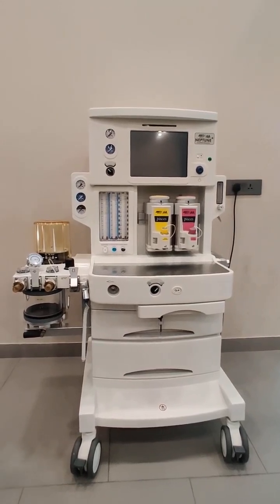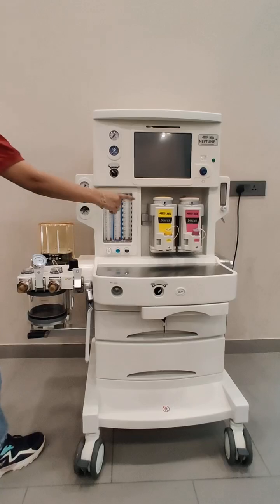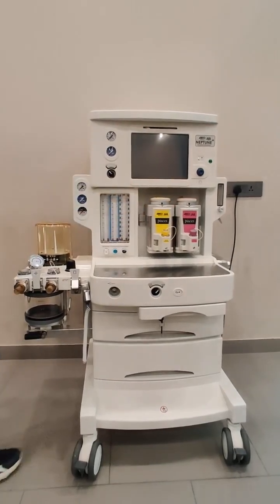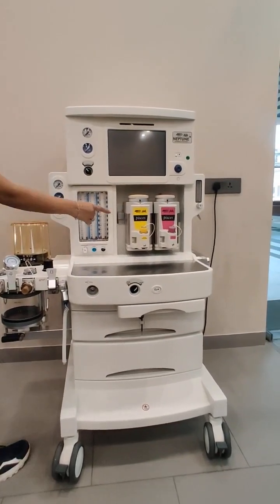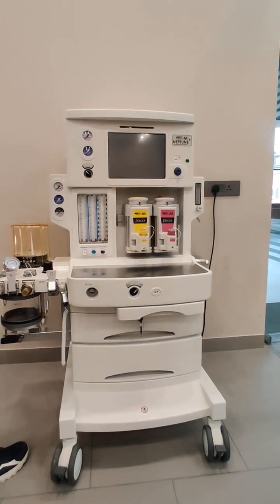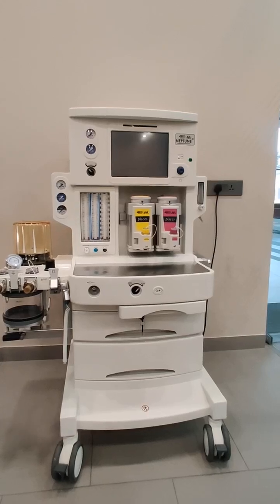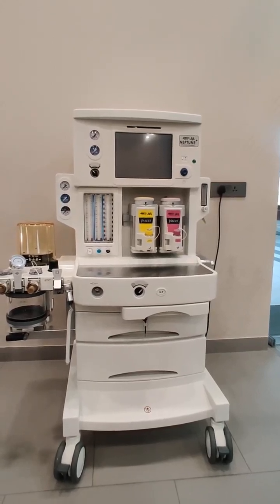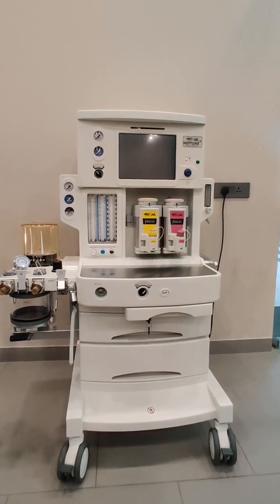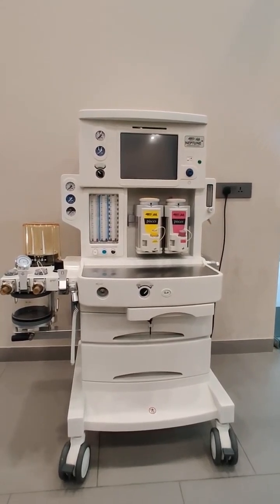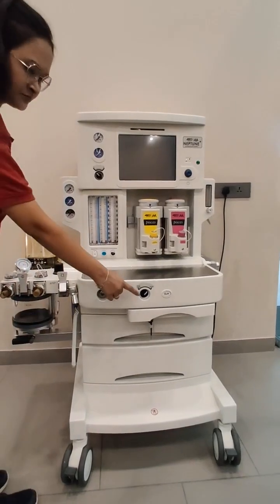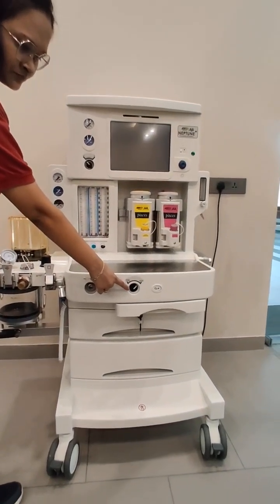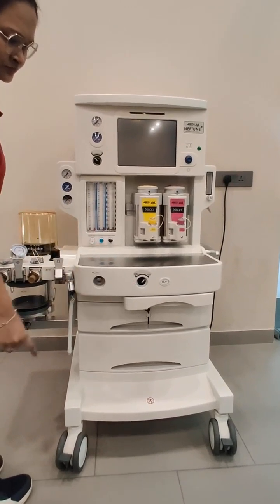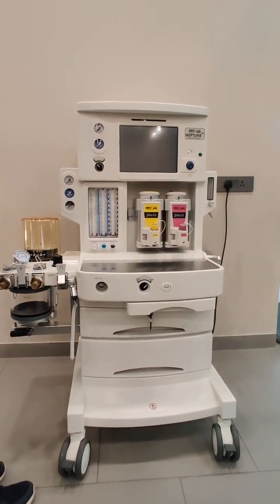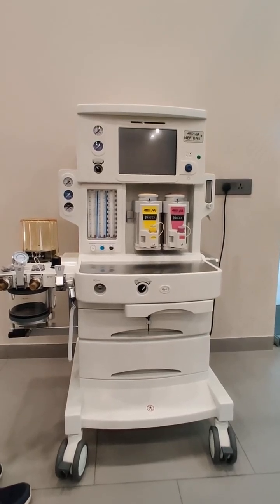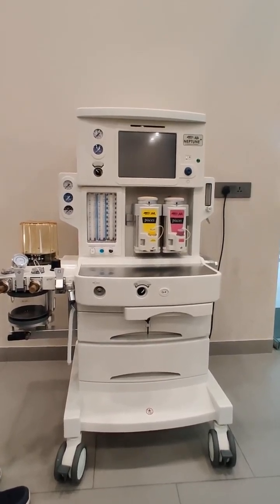So we have the connector for connecting 2 vaporizers at the same time. Right now it has been connected with 2 vaporizers: one is sevoflurane and the other is isoflurane. You can take the output of the anesthesia gases either from the open circuit or from the closed circuit. So we have the changeover knob over here. You can control the output either from the open circuit or the closed circuit, and the same will be shown on the ventilator screen also. In whatever mode you are operating the machine, that will be displayed on the ventilator screen also.